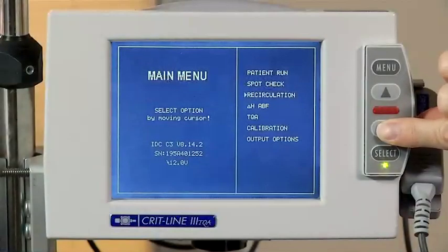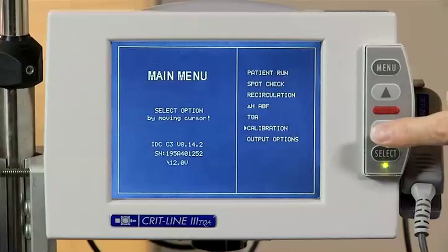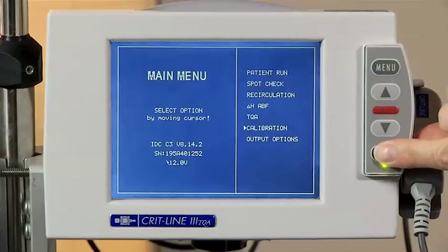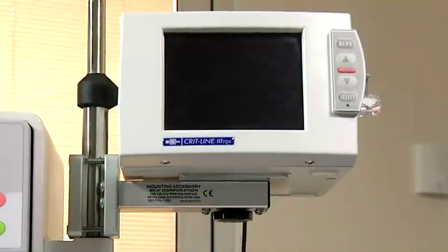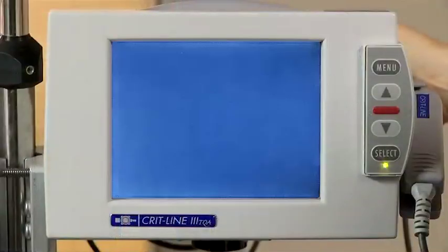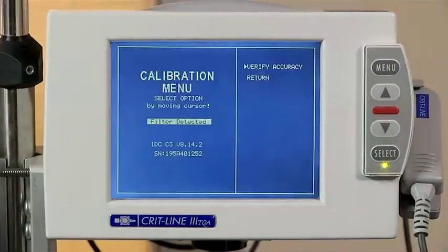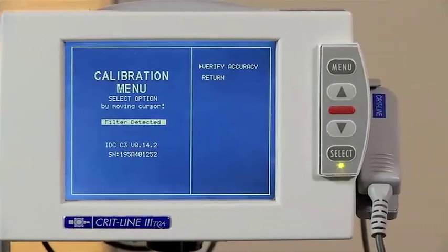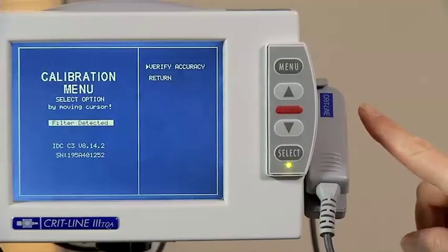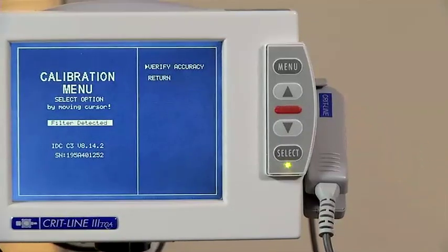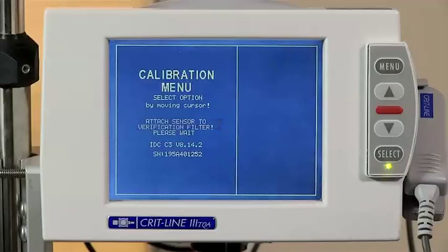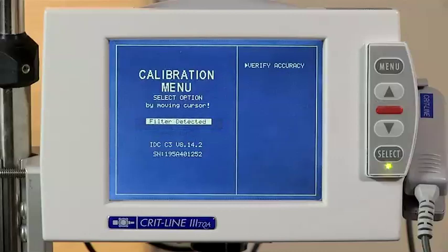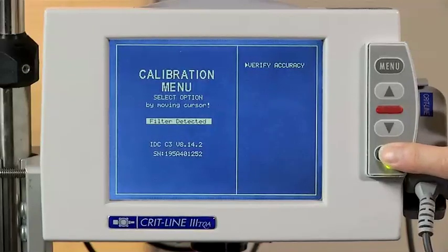To verify the accuracy of the CritLine monitor, you can scroll to Calibration from the main menu and press the Select button. If more than 30 days have passed since the last time you performed a Verify Accuracy test, you will see the Calibration menu when you turn the CritLine monitor on instead of the main menu. Make sure that the sensor clip is placed on the verification filter on the side of the CritLine monitor. Wait for the CritLine monitor to detect the verification filter and to display the filter detected message. Once you see this message, move the cursor to Verify Accuracy and press the Select button.